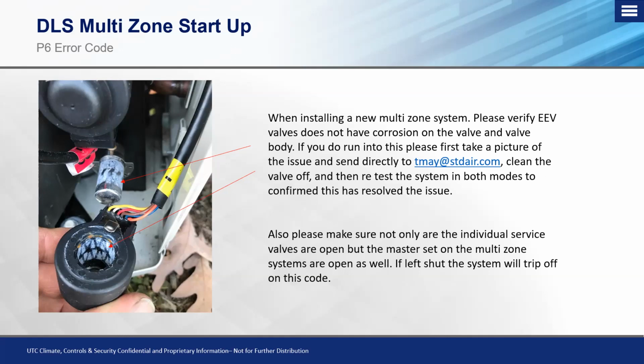If you confirm that your charge is correct, the next thing that I'm going to tell you to check is taking the valve off of the EXV post and verifying that you do not have the corrosion buildup like we see here. If you do have that, please take a picture of it like you see here, and then go ahead and you can take some soapy water and a rag and just go ahead and clean that off.